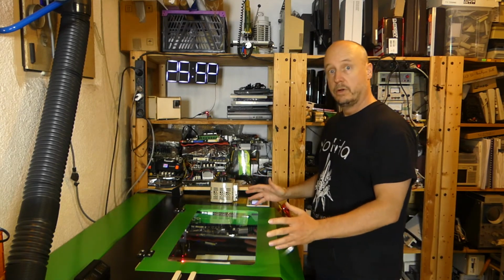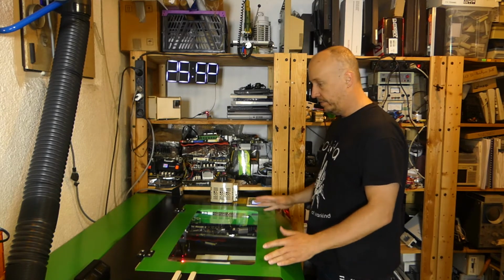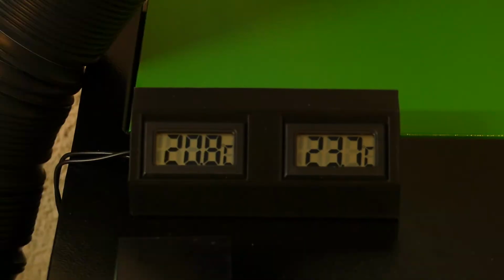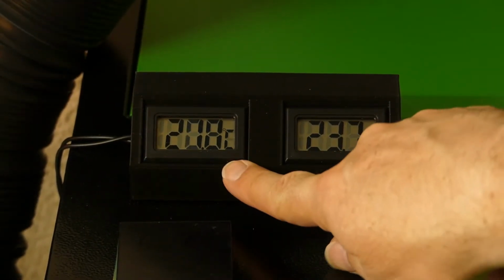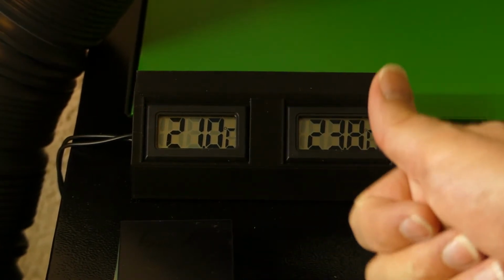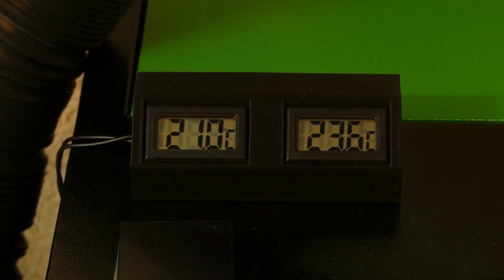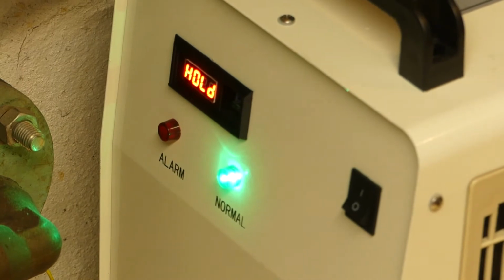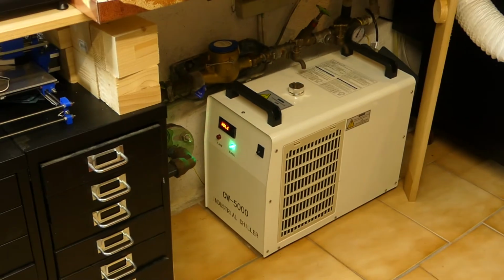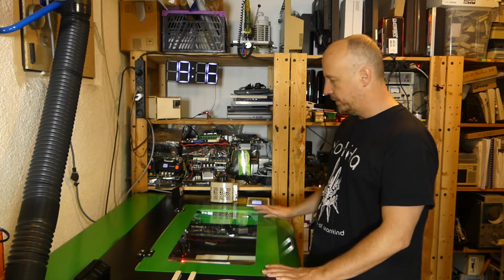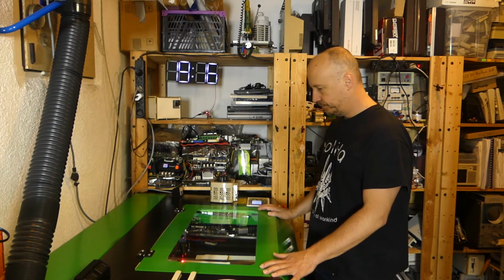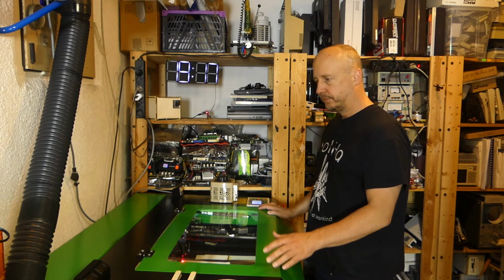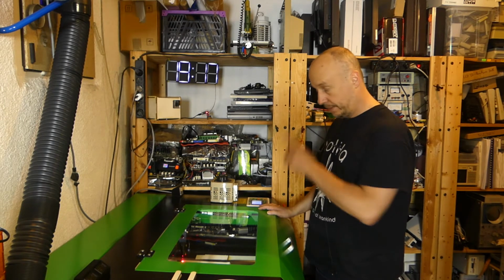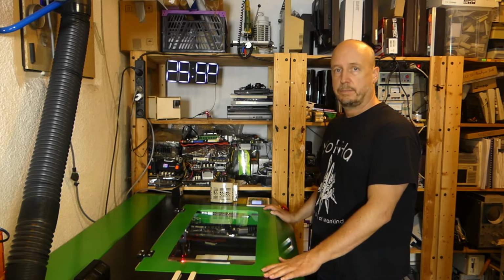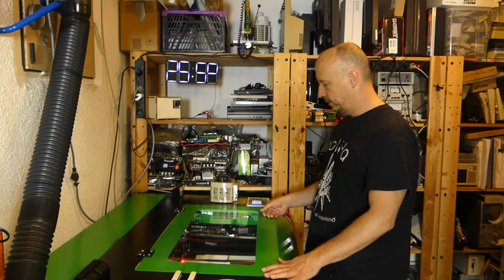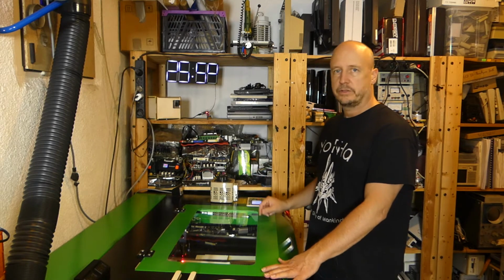This is a really good improvement. Even now that it's been running all day, my laser tube is at 23.7 degrees. My water return temperature is at 20 degrees on the outside of the tube. The sensor on the chiller says it's between 16 and 17 degrees. That is exactly the way I want it. And the power of the laser tube has been improving ever since, so it does need run-in, and it's been getting a lot better. Maybe I want to spend some more money and get some better lenses, or at least another set so I can have different focal distances.